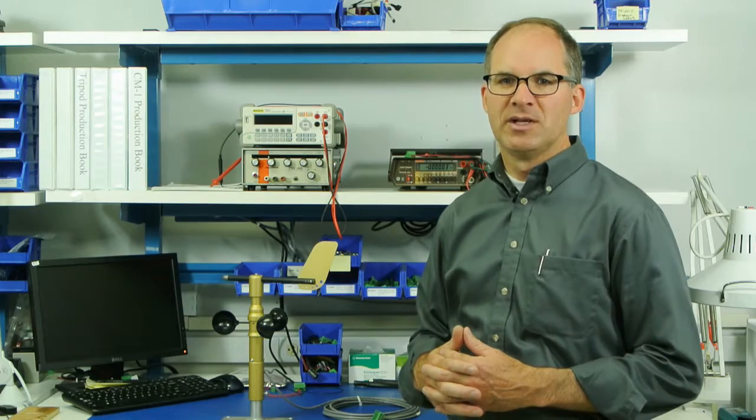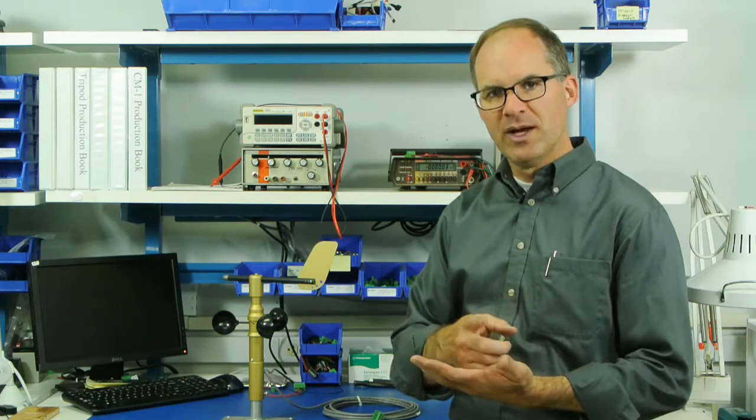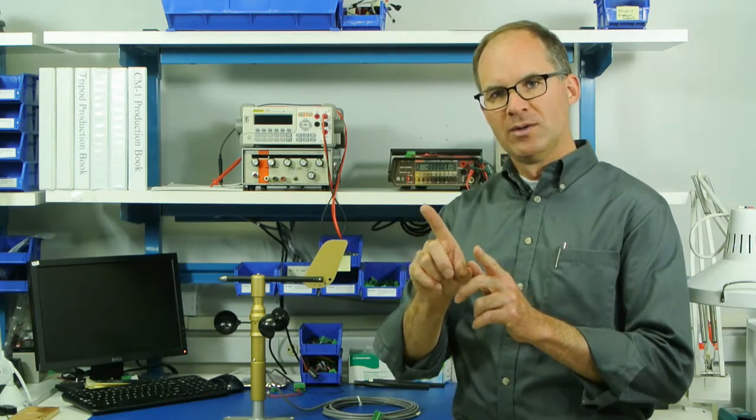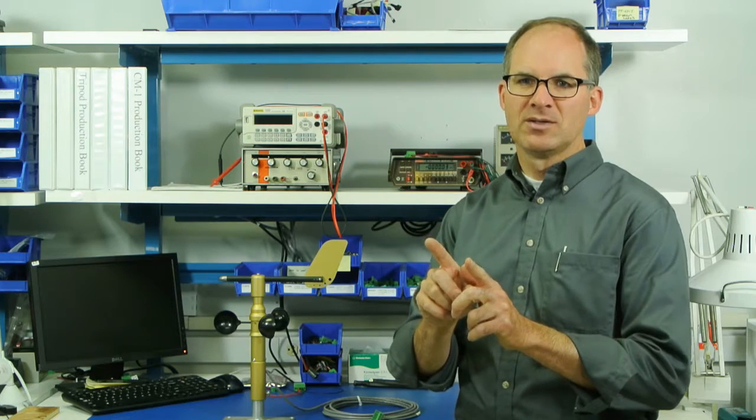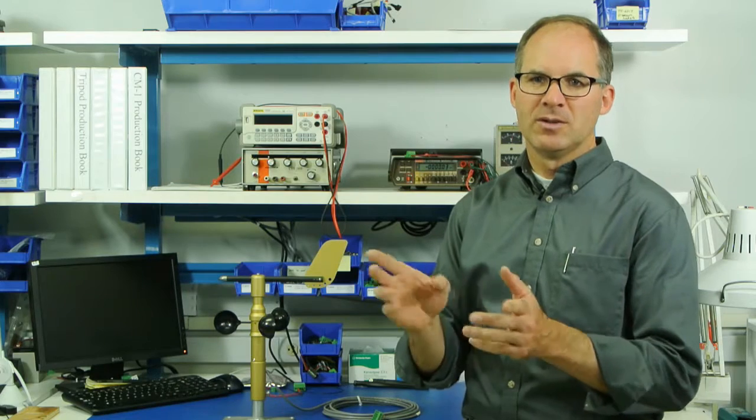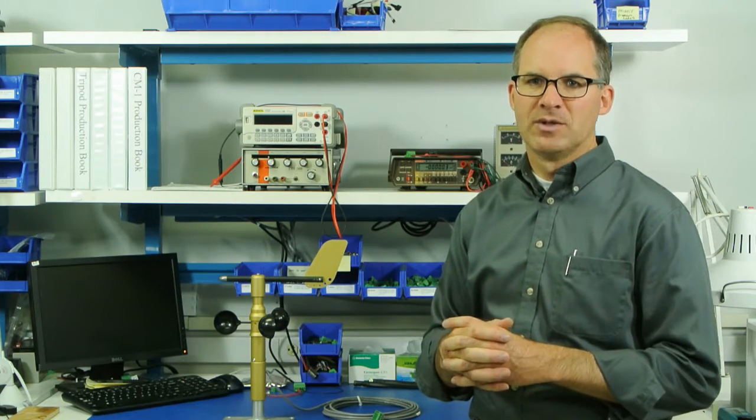Most wind direction sensors use a potentiometer. Potentiometers consist of a resistive band that starts at a low resistance and goes to a high resistance. So by measuring the value of that resistance, the instrument knows what direction the wind is blowing. The drawback to that is you have a transition from the low resistance to the high resistance. So all wind sensors that use a potentiometer have a dead zone. That dead zone can vary from a few degrees to up to 5 degrees, depending on the sophistication of the potentiometer that's used.